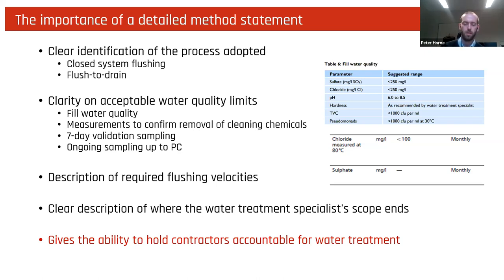There's a bit of a misalignment in the chloride levels here. And chloride can increase the risk of corrosion, and we want to maintain and limit that as much as possible. Chloride can only really get into your system through your fill water line. And particularly in London, chloride levels are between 60 and 80 milligrams per litre.